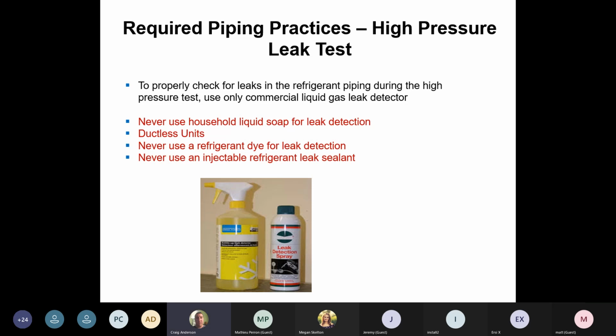So, required practices if you're leak checking. We don't recommend household soap. We don't know what's in there, and if it does get in the lines, we don't know what kind of damage it's going to do with the internal oil. So there is commercial leak detection spray out there, or soap that you can use that's rated for refrigeration use. Buy the right stuff, use that to do your leak checking.